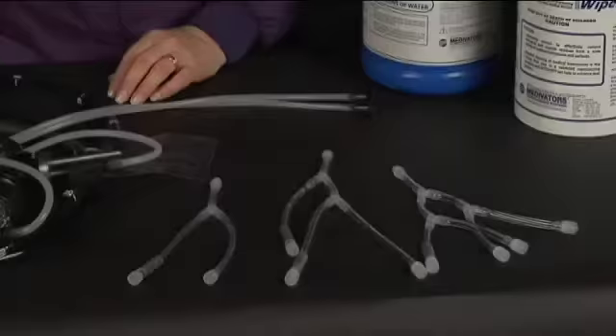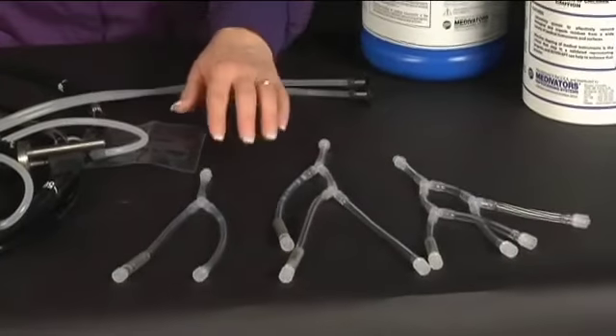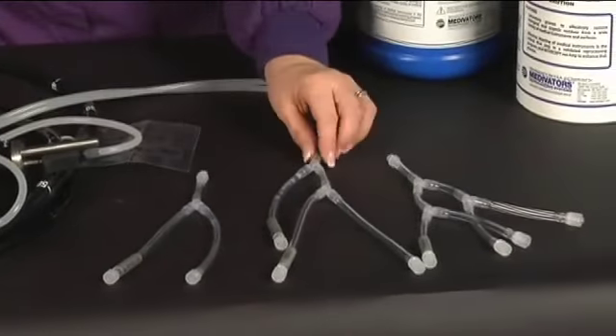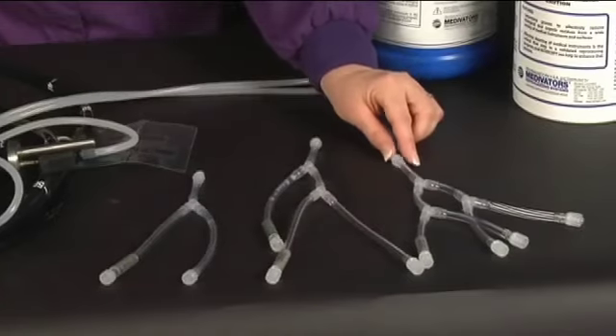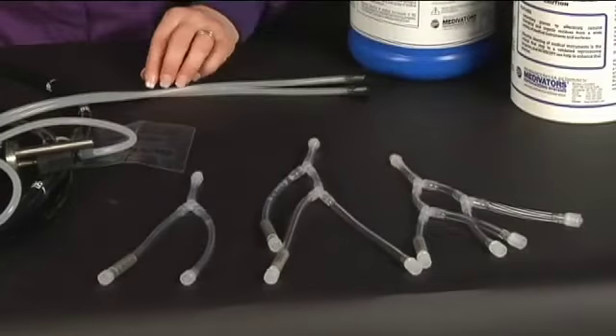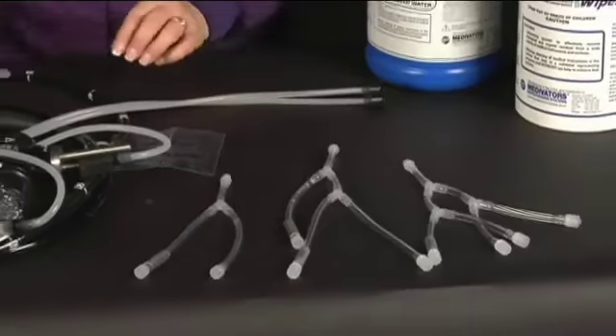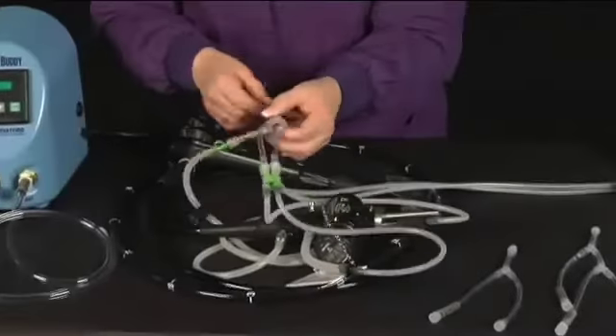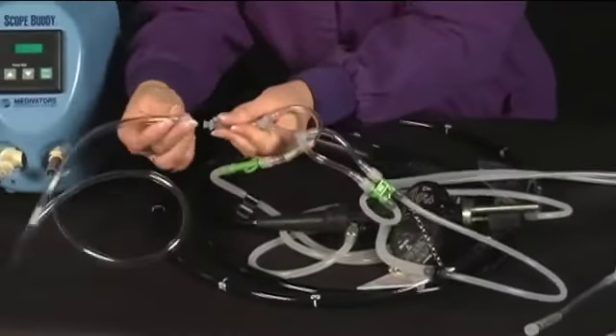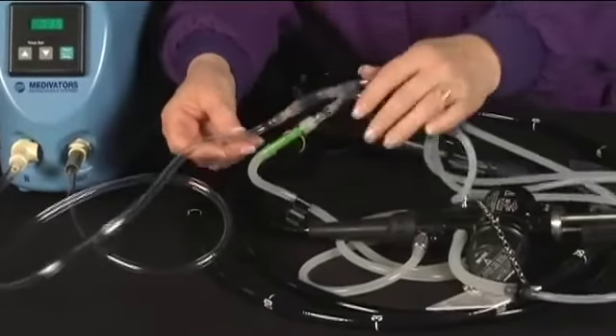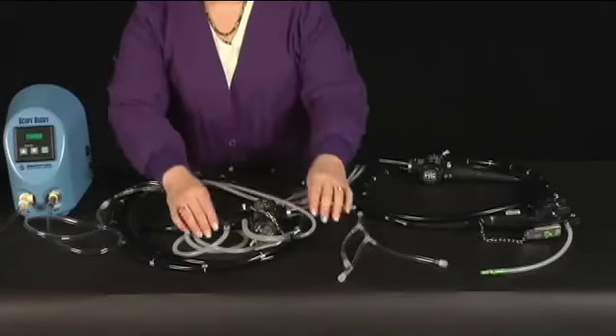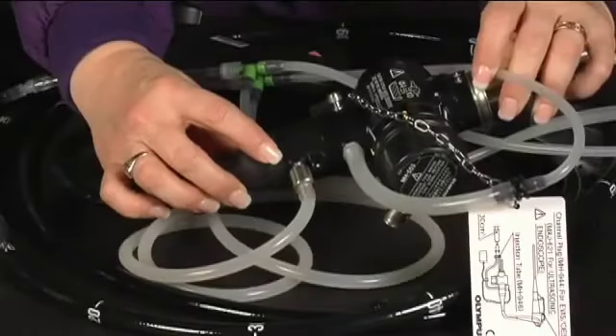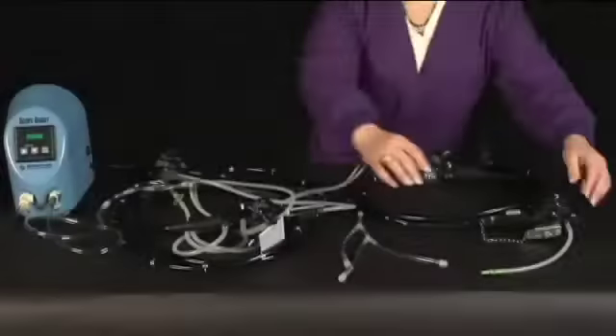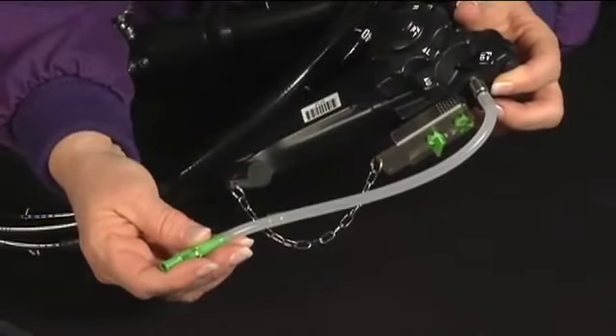Select the appropriate Scope Buddy universal cleaning adapter, 2-way, 3-way, or 4-way, for the endoscope being cleaned and attach it to the universal cleaning adapter extension line. Attach the ends of the selected universal cleaning adapter to the endoscope manufacturer's channel cleaning adapter and, if applicable, to the flushing tube for the auxiliary water inlet, forward water jet, or elevator wire channel.